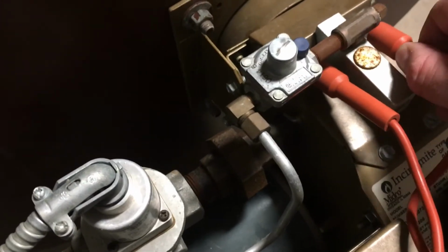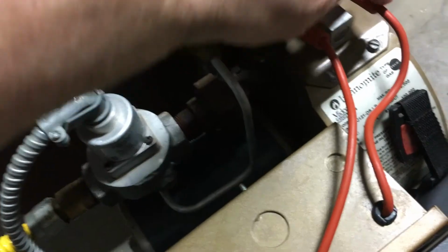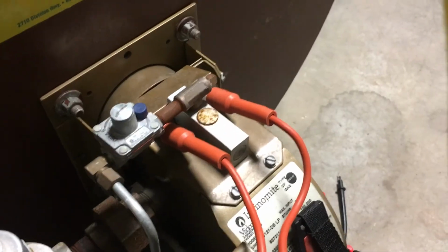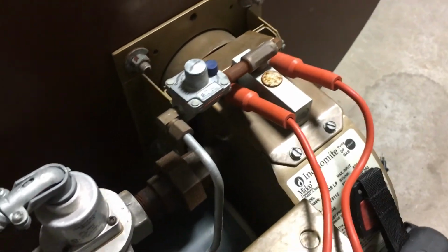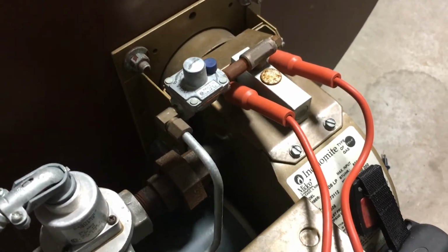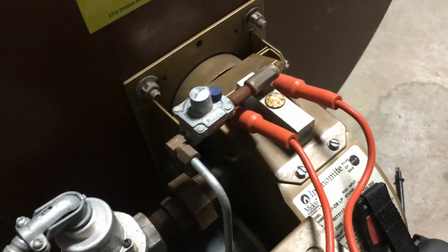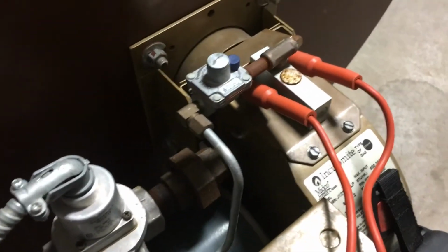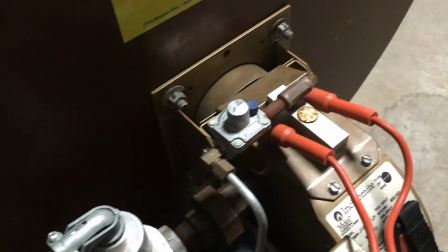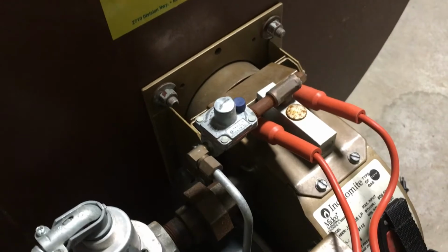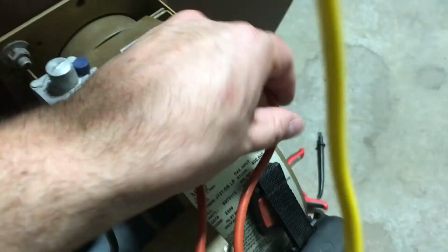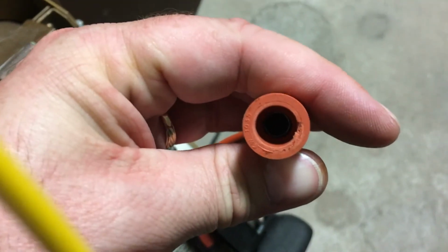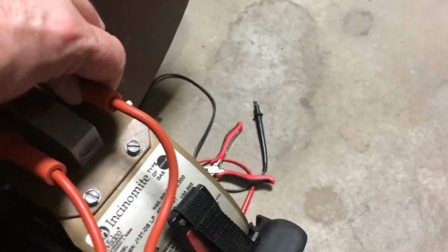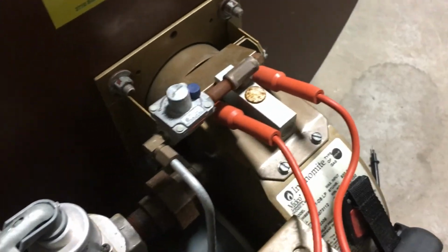You won't be able to see it, but you need to verify that you're getting spark between the wires and ground to verify everything is sparking properly from the electronic control. And again, you want to get an 1/8 of an inch gap between the terminal and the ground. How are you going to verify spark? Normally, as long as you hear the spark, you can see the spark, it's fine. If you do not, just verify that the wires are good, you have good connections inside there. It's tough to see, but nothing is cracked, nothing is broken. That's the one thing you need to verify, that you have good connections and good wire all the way through.